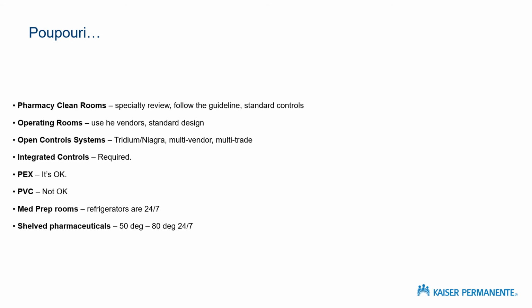We do have standards that we want open control systems. So we are looking for multi-vendor control systems, multi-trade control systems. That tends to be Tridium Niagara. And so we do have a preference towards that. We require integration of our controls. And so if you're doing a project that involves lighting controls and HVAC controls, make the decision early on. First up, it's required by our standards that you make the decision to integrate those controls. Don't find yourself at the end of a project saying, well, I didn't think that we were going to put the lighting on the same system, because it absolutely is an expectation.